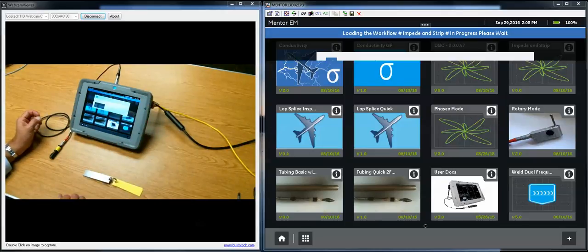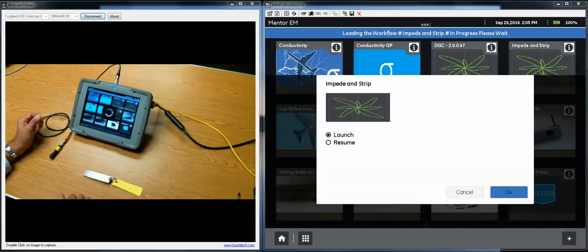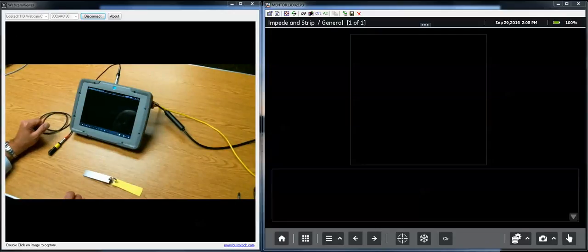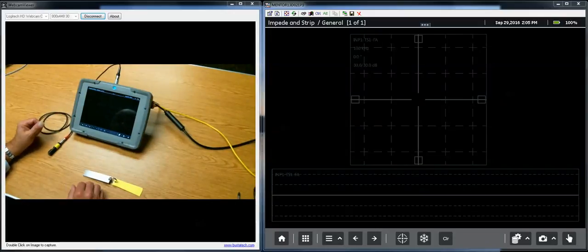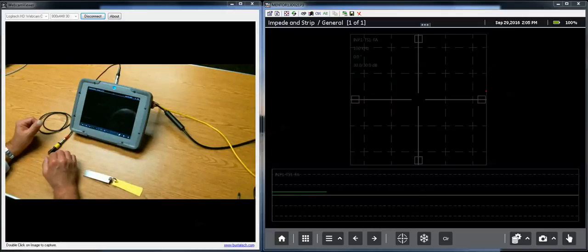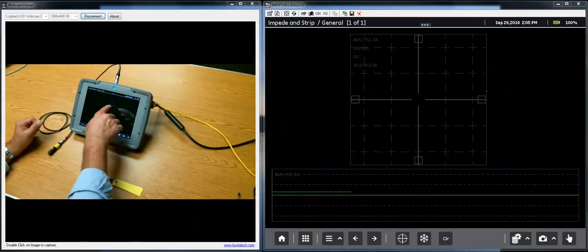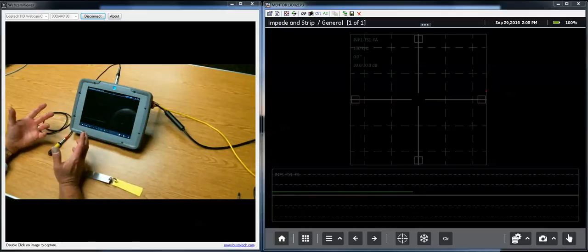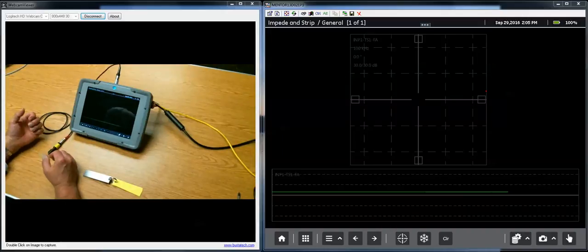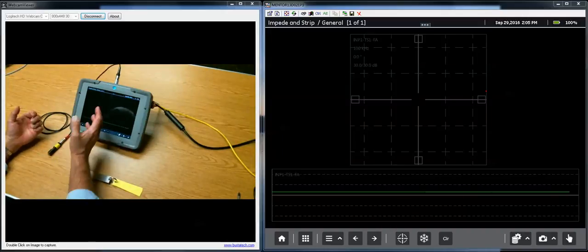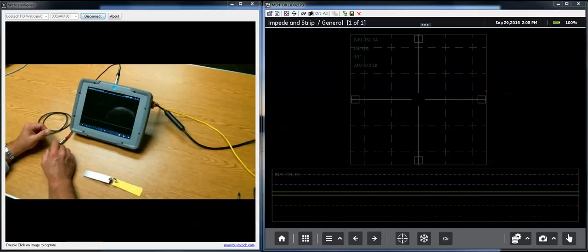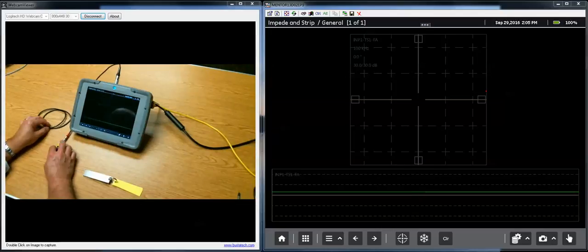We'll launch that now. We haven't done anything with instruction in this app, it's just very simple and straightforward. We have a Lissajous display, also known as a spot view or impedance plane view on the top, and on the bottom of the screen we have a strip chart. So the two basic views.